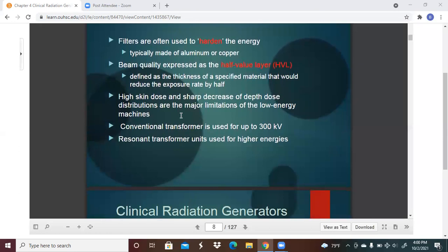So we put in some filters there to harden the energy. In other words, we're going to take out some of the stuff that's not going to do anybody any good. And those are typically made of aluminum or copper. The beam quality is expressed as half value layers, or HVLs, defined as the thickness of a specified material that would reduce the exposure rate by half. That's why they call it a half value layer. So high skin dose and sharp decrease of depth dose distributions are the major limitations of low energy machines. They just don't penetrate that deeply. So a conventional transformer is used for up to 300 kV, and resonant transformer units are used for higher energies.